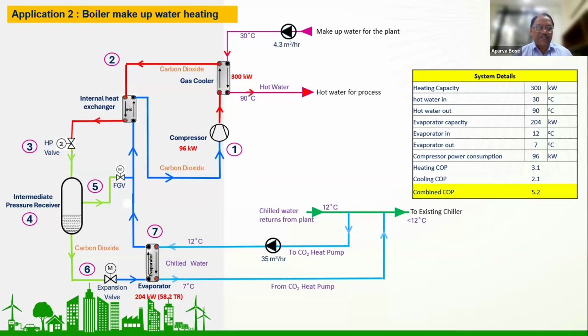If we talk very specific to this particular case, here we have a compressor which is giving the CO2 temperature at 125 degrees Celsius at 115 bar. And moving on, once the water comes in at 30 degrees Celsius, it goes out at 90 degrees Celsius. Then this CO2 at 115 bar and 32 degrees Celsius goes to the internal heat exchanger, where again the temperature comes down to 27 degrees Celsius before it goes through the HP valve, which is the high pressure valve.